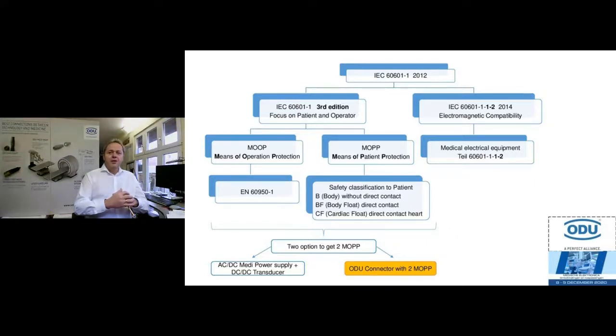And for that reason, we have three classifications. You will find this classification on my screen. We start with B, which stands for body, and this is without direct contact from any electrical things to the body of the patient. Then we have BF, the body floating, which is the direct contact with a cable, for example, ECG, which has a cable and a sticker on the body, and you have a connection to electrical equipment.